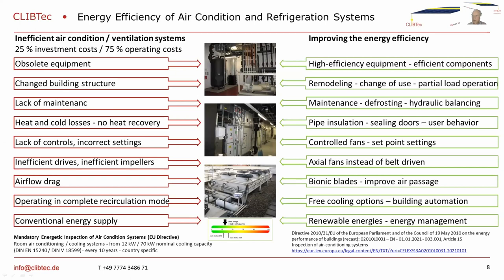In many regions, outdoor air temperatures are below 21 degrees Celsius for more than 4,000 hours a year and are suitable for free cooling. An important point is also the change in user behavior, for instance leaving doors open to cold storage rooms.